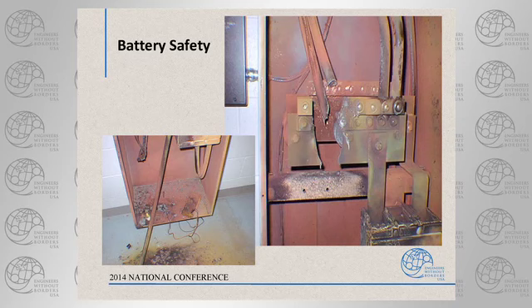Ready? Yeah. All right, battery safety. This will get your attention. This was a UPS string, 540 volt DC, large flooded cells. The contractor is cutting a battery cable with a pair of wire cutters, basically like a pair of limb loppers. 2.5 foot leverage to cut the wire. The wire was either 500 or 750 kcmil. So this wire is twice the size of your thumb in diameter and designed to carry, well, let's see, if it's 500, that's 400 and some odd amps. If it's 750, it's about 600 amps that it's designed to carry.